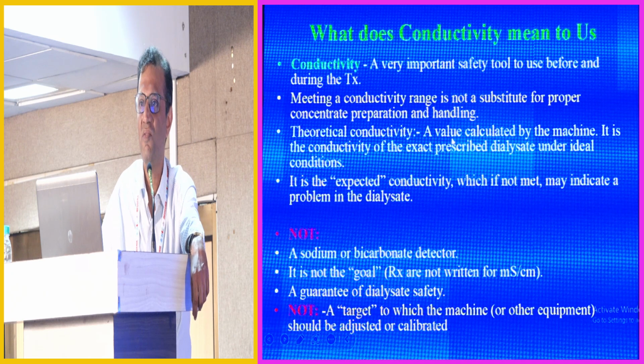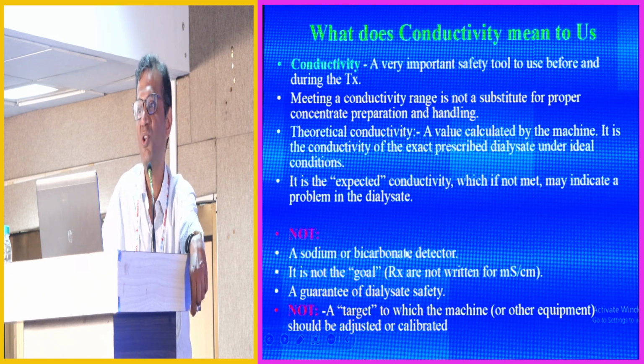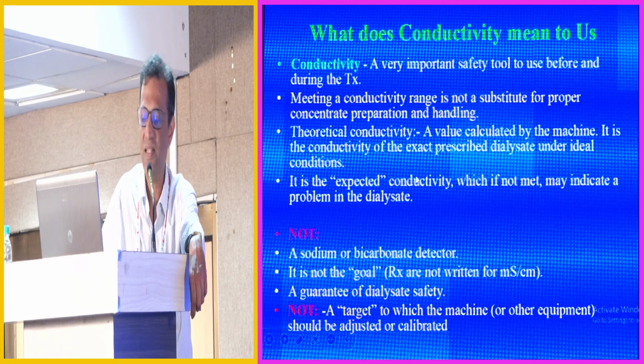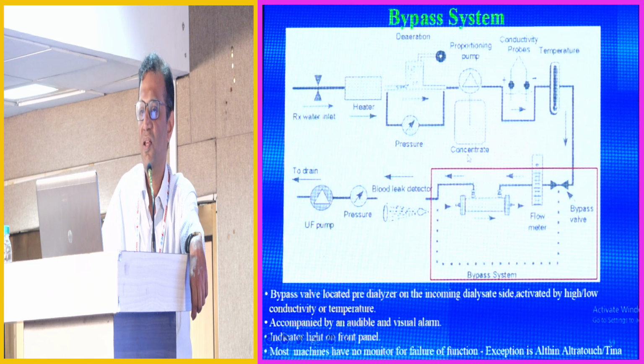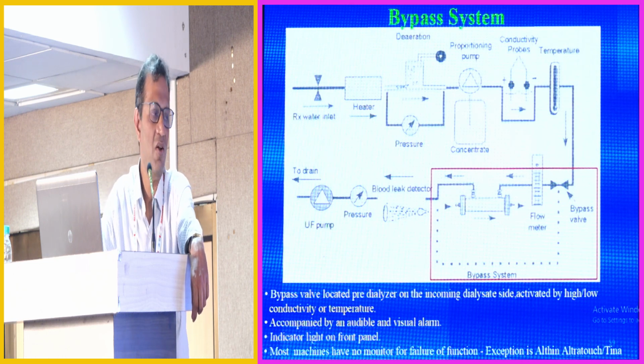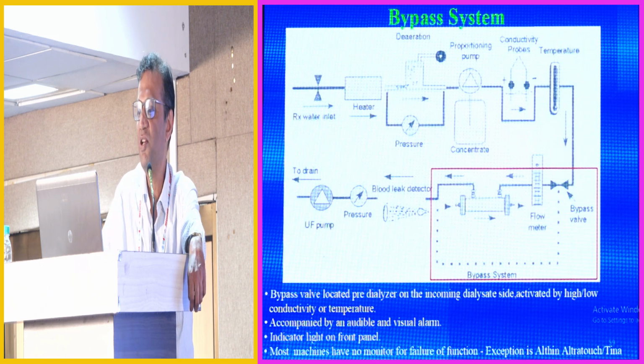This machine will not alarm even if there's no bicarbonate coming in. So what is conductivity? It's an important safety tool during the treatment, but it's not a sodium or bicarbonate detector, and it's not a guarantee of dialysate safety. So if the conductivity or the temperature are wrong, the machine needs to bypass the dialysate to the drain rather than send it to the dialyzer.